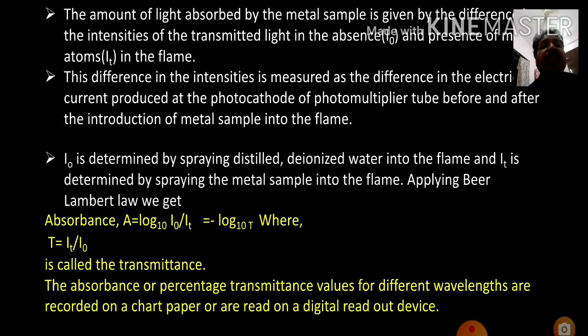I0 is determined by spraying distilled deionized water into the flame, and IT is determined by spraying the metal sample into the flame. By applying Beer-Lambert's law, we get absorbance A is equal to log to the base 10 of I0 upon IT, that is equal to minus log to the base 10 of T, where T is equal to IT upon I0. That is nothing but what is called transmittance. The absorbance or percentage transmittance values for different wavelengths are recorded on a chart paper or read on a digital readout device.